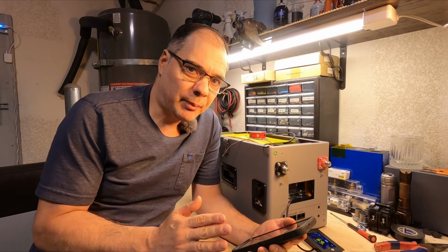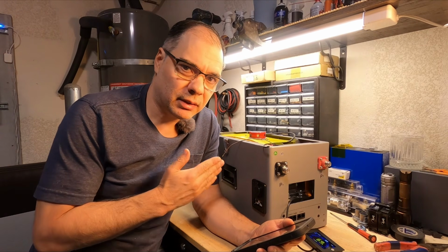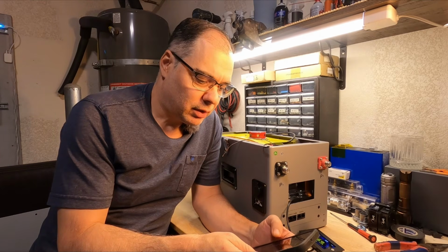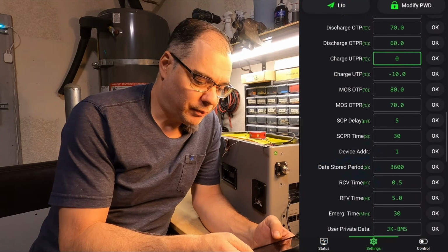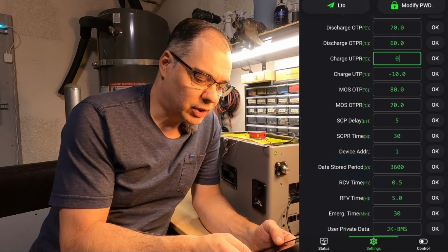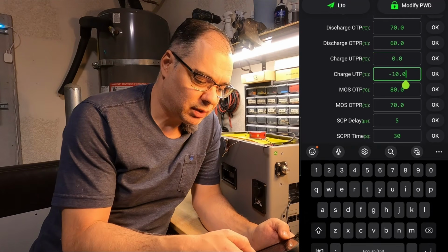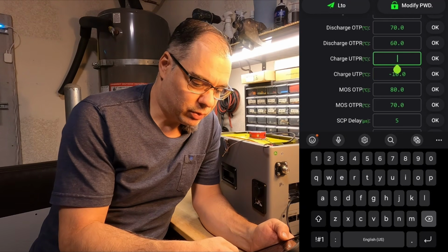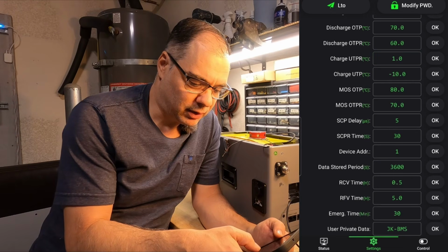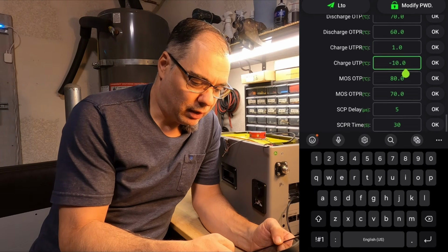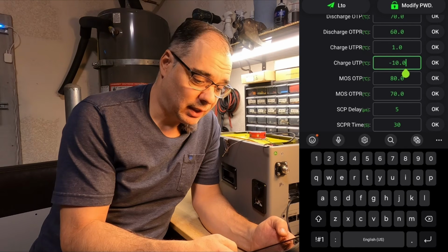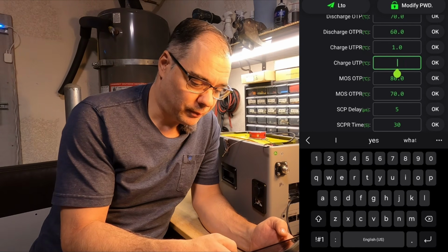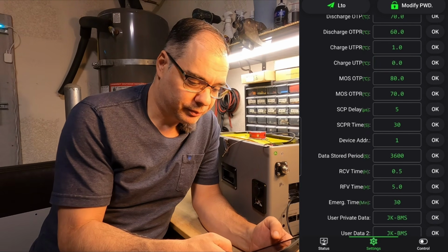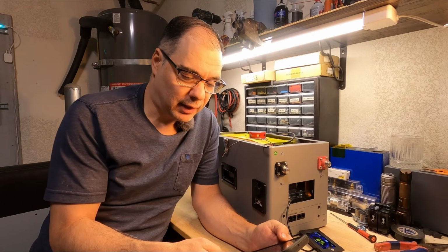Okay, so we're going to do a low temp and a high temp cutoff test on these temp sensors. So in the BMS settings, the under temperature protection return is 0 Celsius. So we need to put that to, say, 1 Celsius. And then the under temperature protection is negative 10 Celsius, so that's too cold. Let's put that to 0. And let's test it out.